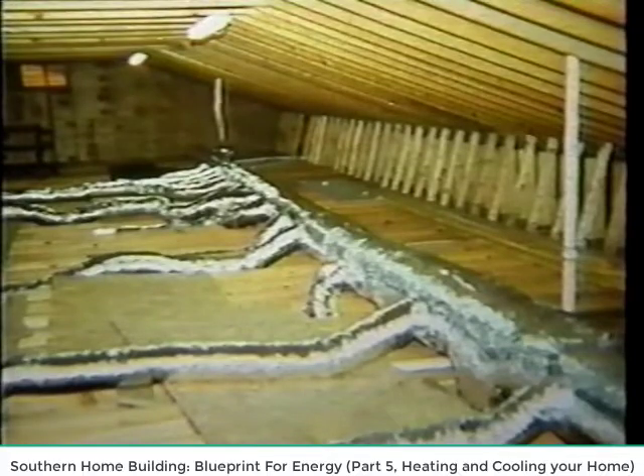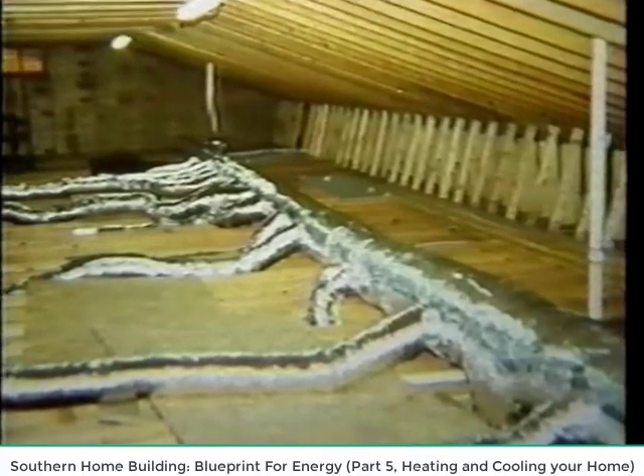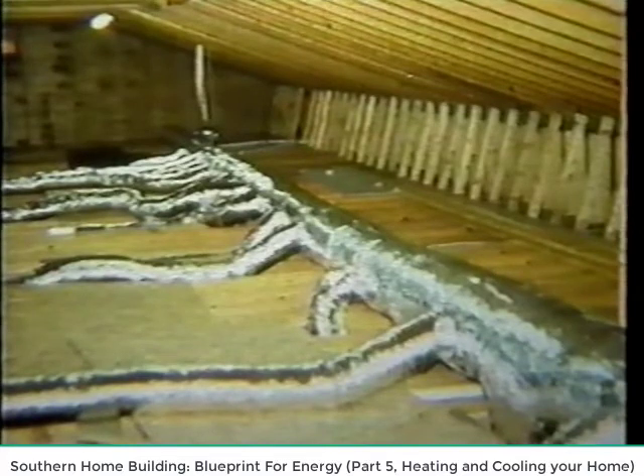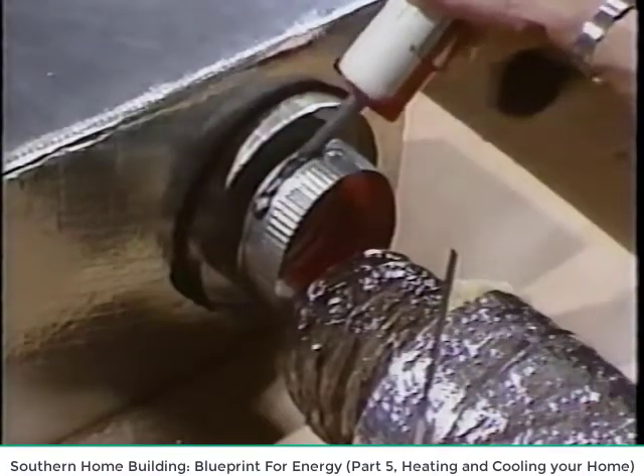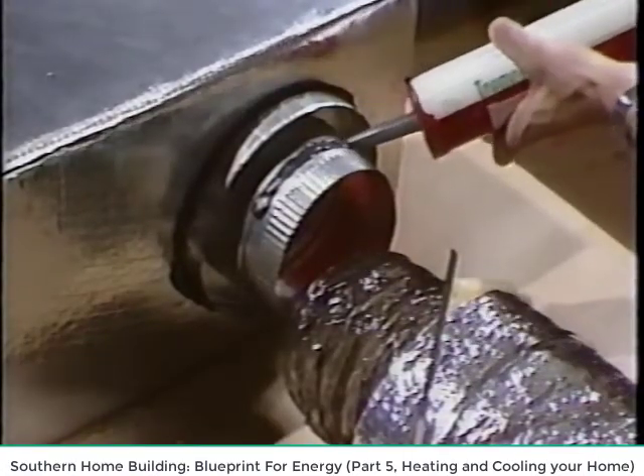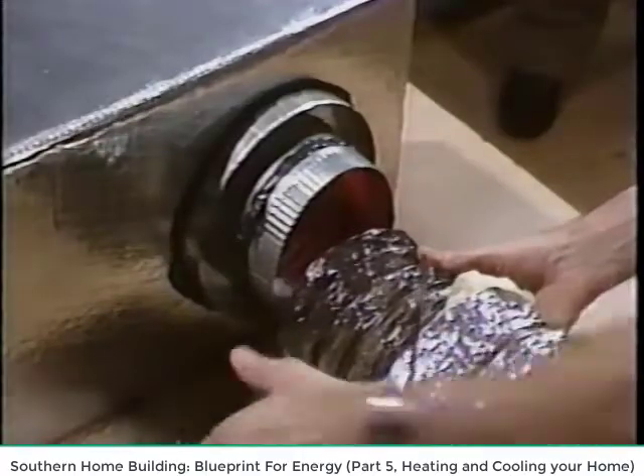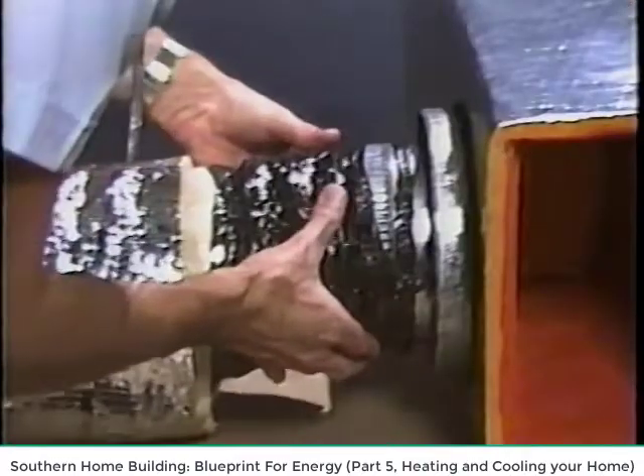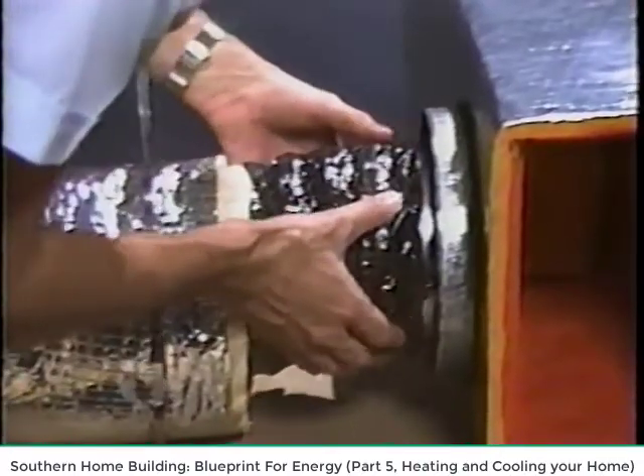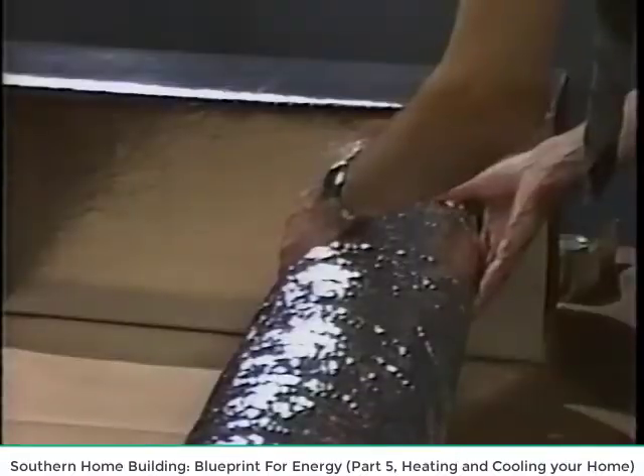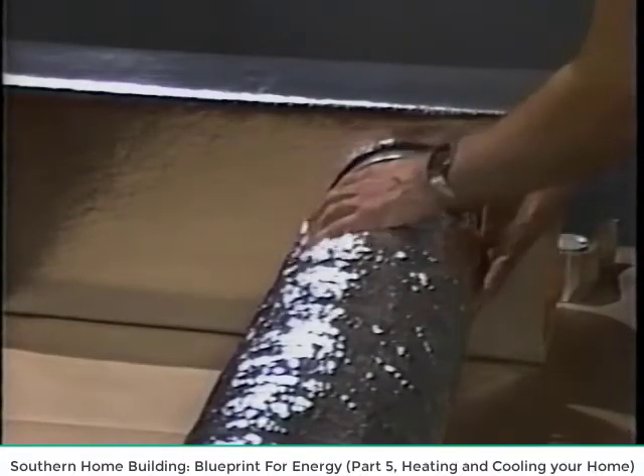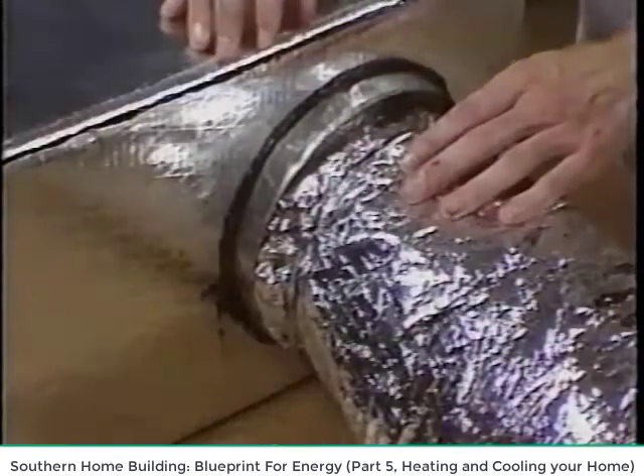The third type of duct is flexible plastic duct, called flex duct. If great care is taken to overcome its tendency to leak at joints, it can be made fairly airtight. To comply with the energy code in Florida, flex duct should be sealed using a thick sealant, like this one called a mastic. Gaskets or tapes can be used instead of mastic, and soon superior tapes with acrylic adhesives will be available. In addition, all flex duct must be fastened to the fitting using a strap or clamp.